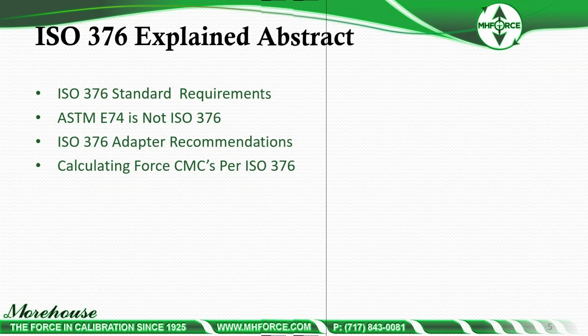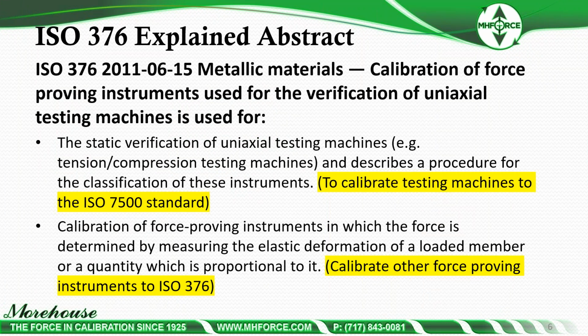Talking about the ISO 376 standard, the current version is 2011, and the full name is Metallic Materials: Calibration of Force-Proving Instruments Used for the Verification of Uniaxial Testing Machines. Basically, the highlighted section is what we're using these for, to calibrate testing machines to the ISO 7500 standard. And it's also used to calibrate other force-proving instruments to ISO 376.